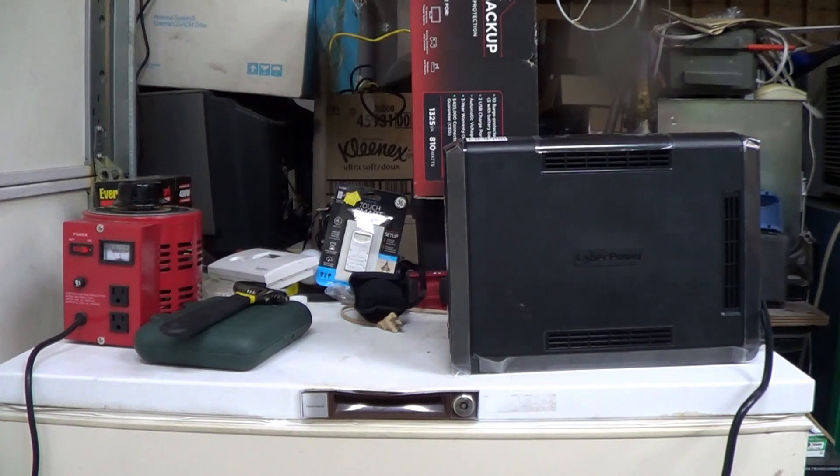So what are we going to do in this video? We're going to revisit the CyberPower SineWave battery backup product review — not because there's anything wrong with it or any deficiency — but because a commenter asked a very good question about a test I had intended to run but left out at the last moment: what this uninterruptible power supply's surge capacity would be. I'm very curious about that, so we're going to answer that question. We'll try starting a few devices — all highly inductive motor loads, probably all hermetic refrigeration compressors — just because that's what I happen to have handy.